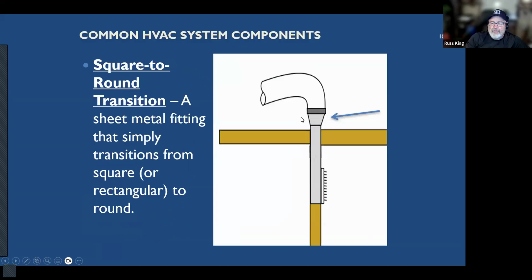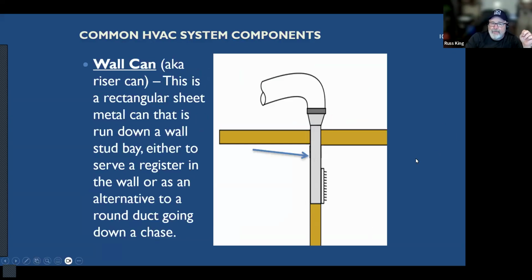A squared-to-round transition is just a way to go from a round duct to a square duct, whether you're going down in a wall can or something like that. There's a lot of different kinds of fittings you'll see, sheet metal fittings. A wall can is a rectangular sheet metal duct that's small enough to fit in between the studs of your walls. Okay. Not a great idea. I would only use those in very desperate measures because they're uninsulated. And so they'll conduct a lot of heat with the sheetrock and stuff, anything it's in contact with. Plus, there's a lot of resistance to the airflow. The air doesn't flow through these very well.